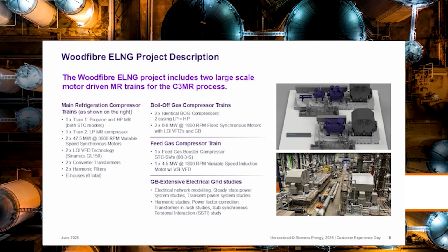And then just really quickly, highlighting again some of that string testing that we did with Woodfibre. A picture down here of the Duisburg string test, the mega test facility that we have there. And a lot of the electrical equipment is not shown, the e-houses, the transformers, and the VFDs, but that was also included in this string testing.